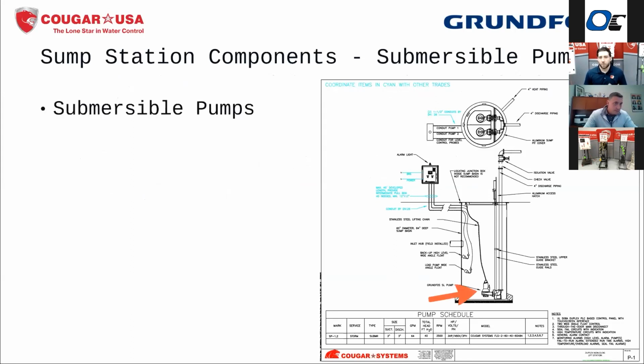So most of the time we're going to be designing around submersible sump pumps. I think there's quite a bit of column pumps in y'all's area that are existing, and maybe some that are going in on new construction. Most of our market is based around the submersibles, but in terms of some of the design and the controls functionality, it's going to be the same whether you're using the submersibles or the column pumps.